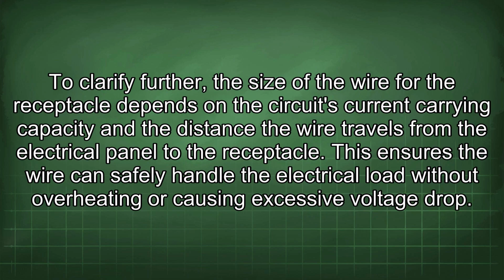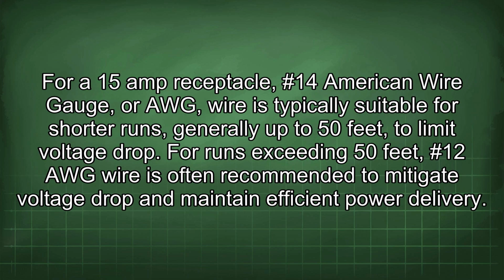To clarify further, the size of the wire for the receptacle depends on the circuit's current carrying capacity and the distance the wire travels from the electrical panel to the receptacle. This ensures the wire can safely handle the electrical load without overheating or causing excessive voltage drop. For a 15 amp receptacle, #14 American wire gauge, or AWG, wire is typically suitable for shorter runs, generally up to 50 feet, to limit voltage drop.